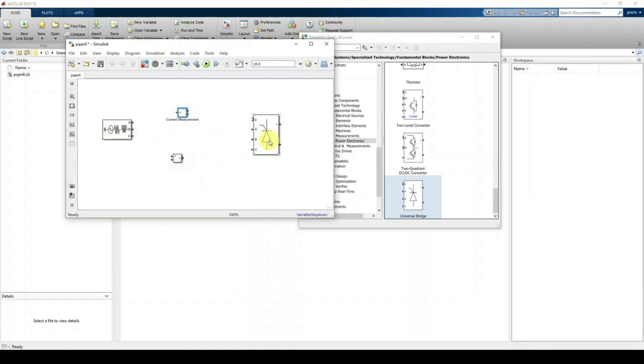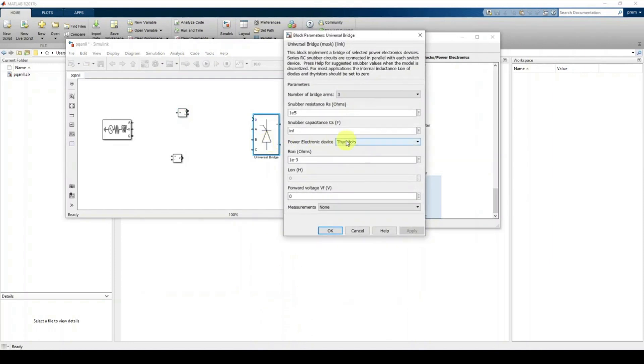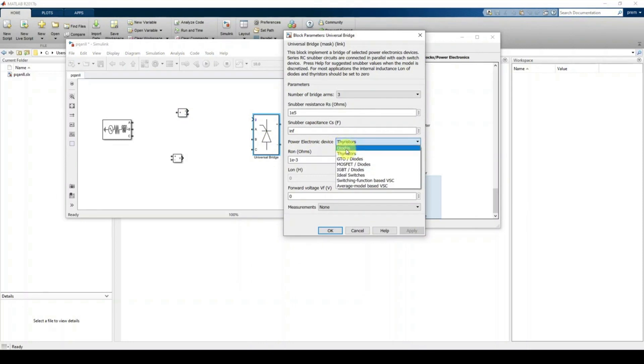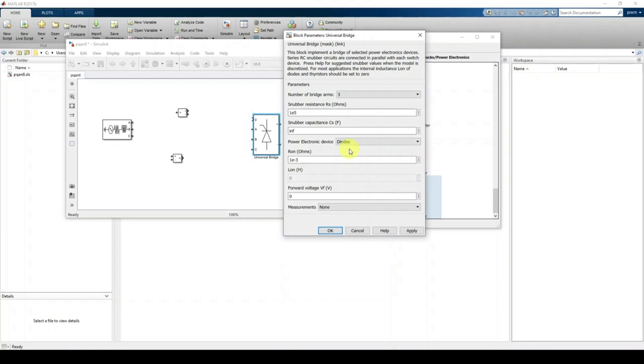Next, we need a diode. Here you can see different options — we need to use diodes with a load connected, acting as a nonlinear load. Because of this nonlinear load, the source current becomes non-sinusoidal, so the power quality is affected. We need to measure the Total Harmonic Distortion when a nonlinear load is connected to the AC source.